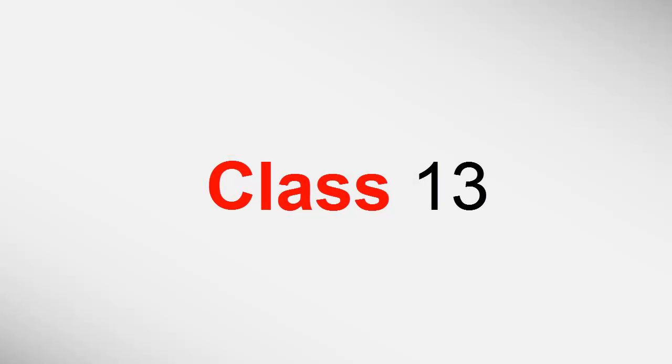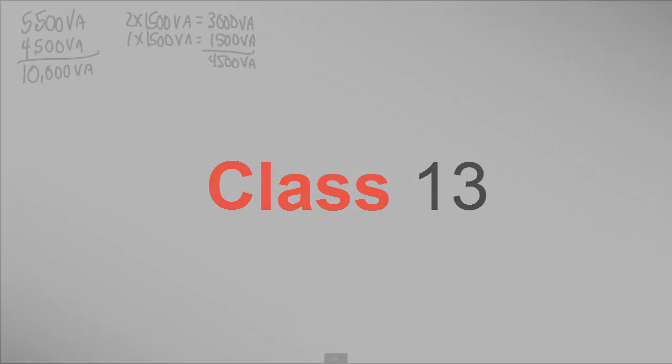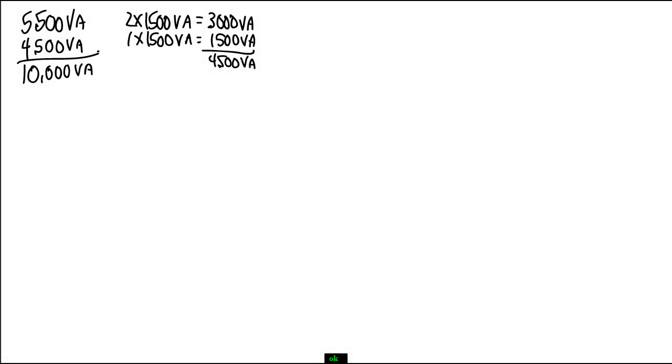Alright, we are at class 13, well over the hump, headed towards the end of the quarter. Let's get back to our calculation that we started or ended with at last class. As you can see, I have a similar calculation here at 5,500 VA for our general lighting load. Then we have our two small appliance branch circuits and our one laundry circuit. That gives us another 4,500 VA for a total of 10,000 VA for our general lighting load.